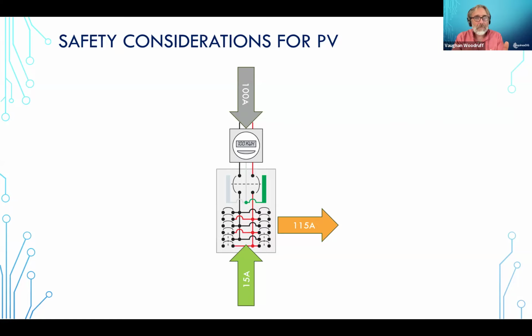This happens all the time because what the code specifies, and I think it was noted in the Q&A, is that as long as the source from the solar is at the opposite end of the panel as the source from the utility, we're not going to get overheating. It's going to be distributed in the way that the loads go through, right? Things are going to be safe.